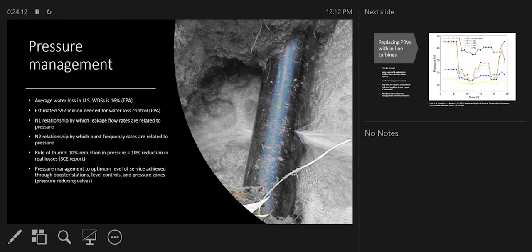Pressure management is generally achieved in a network by dividing it, especially in networks that have a lot of differences in elevation. It's achieved by dividing the network into pressure zones, which are supplied by pumps and booster stations and pressure reducing valves, and then also level controls in the tanks themselves.